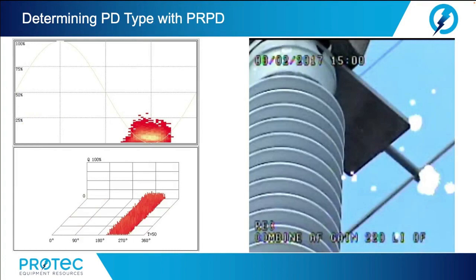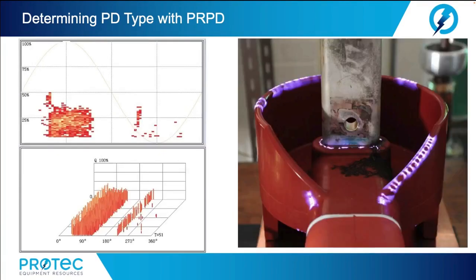Here we see an example of corona discharge. The UHF pulses from a corona discharge are low in amplitude and only occur on the negative half cycle as electrons leave the conductor to ionize the surrounding air. And here we see an example of surface tracking discharge. UHF pulses resulting from surface tracking are typically much denser on the positive half cycle as electrons move from ground to the conductor.